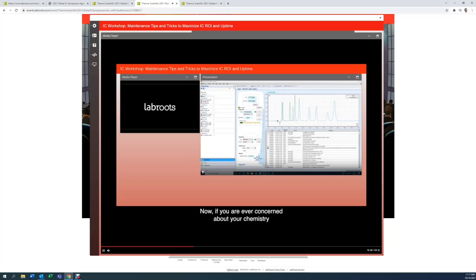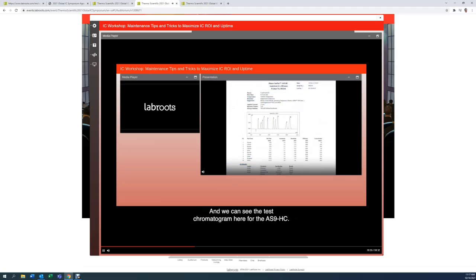Now, if you are ever concerned about your chemistry, and you're running an application which is a bit away from the standard application for the column, every single column comes with a test chromatogram. We can see the test chromatogram here for the AS9HC. On the test chromatogram, the retention time for the last peak, sulfate, is around the 21-minute mark. On our column, it's coming out slightly faster. Also, remember that the test chromatogram isn't produced with a guard column, and the guard column could add around 10% onto those retention times. So the column we were using is slightly worn, but the order of elution is right, and we're in the same sort of ballpark.